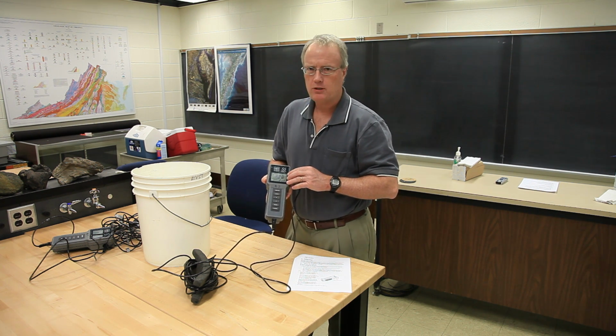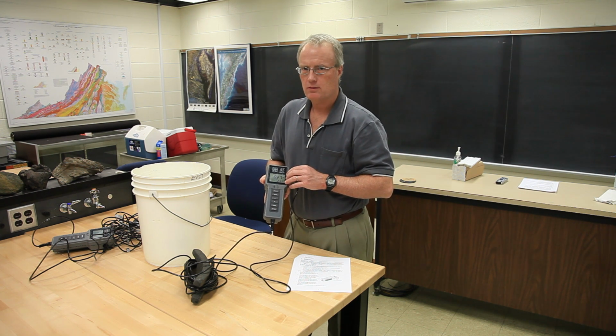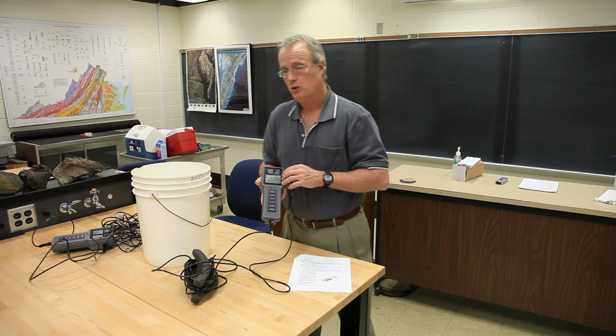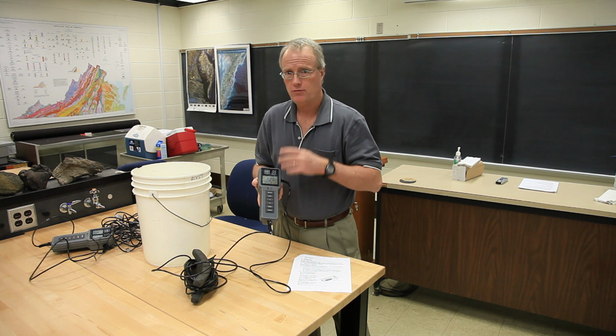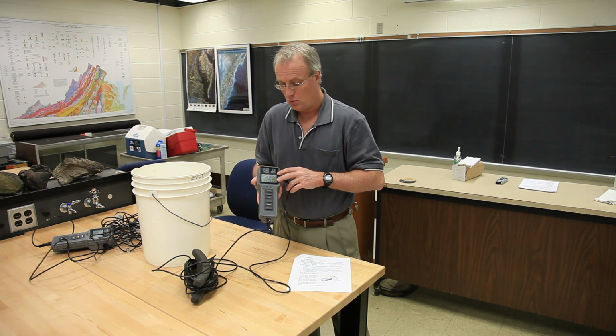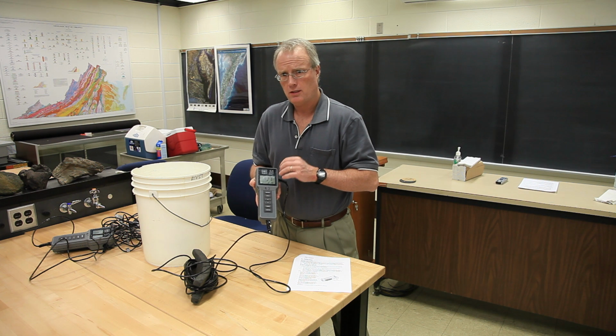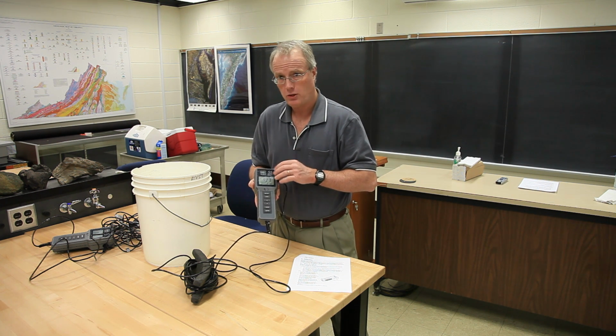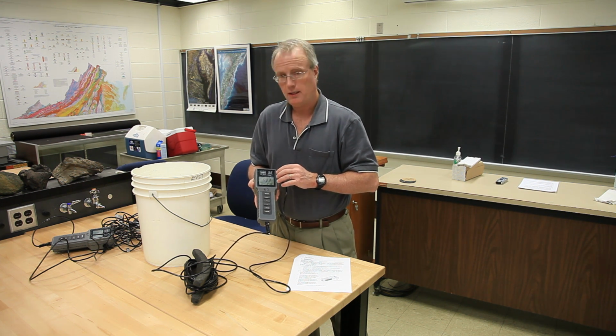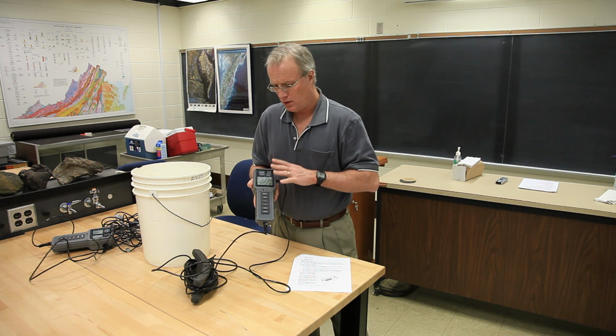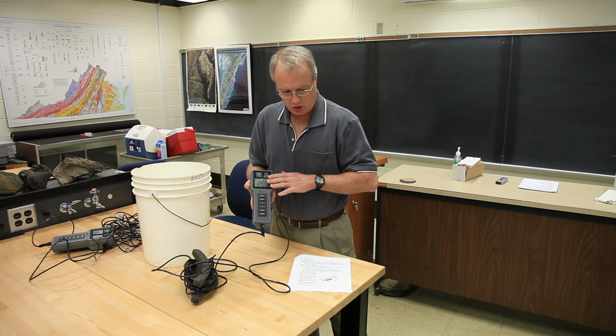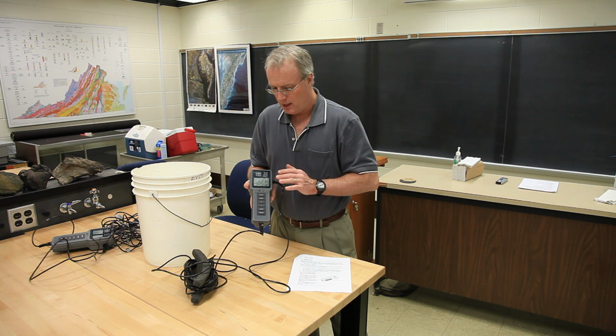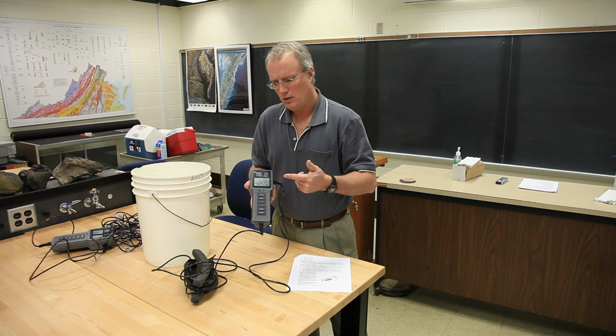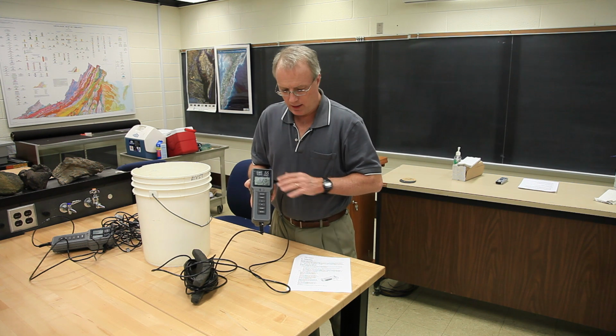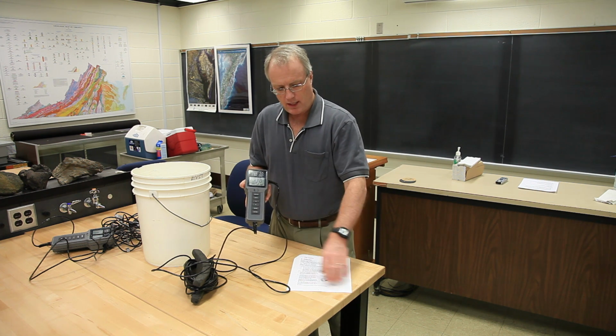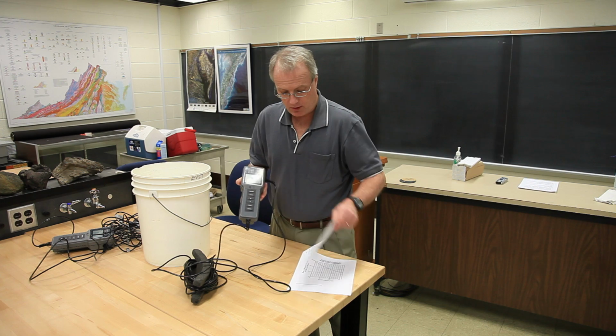To do the calibration procedure, you need to know your elevation in feet to within the closest 100 feet. Ashland is about 200 feet, so if you're in and around Ashland, you're at 200 feet. And you need to know the salinity of your water. For all of the fresh waters that we're going to be working in, the salinity is 0. You need both of those numbers to be able to calibrate this machine. So it's on for 15 minutes, I know my local elevation, I know my salinity, and then I simply read through the calibration steps carefully.